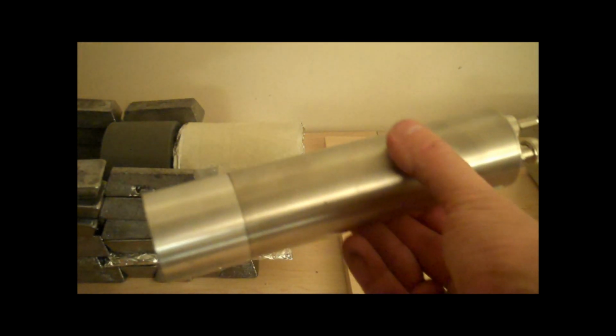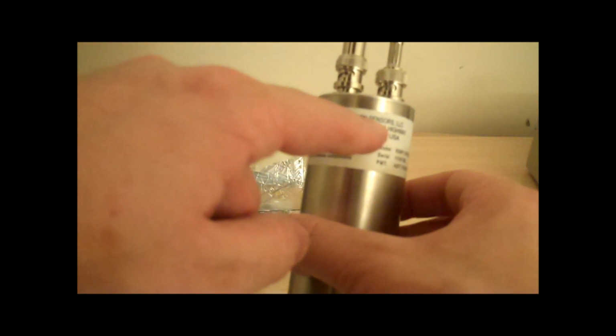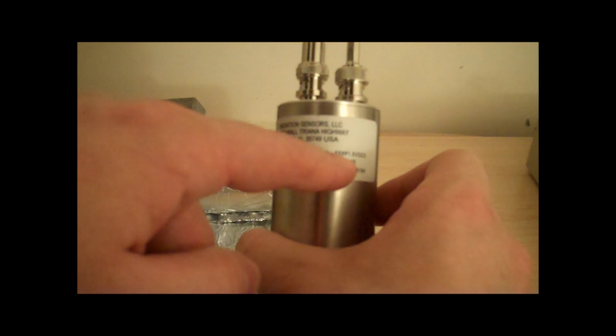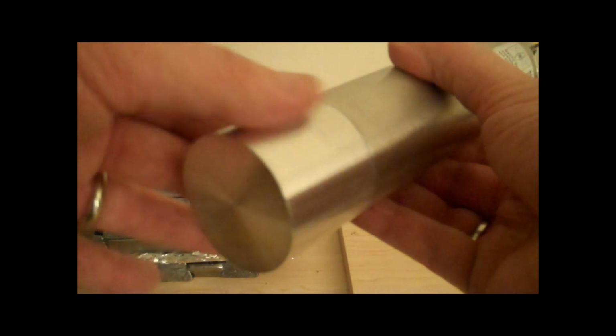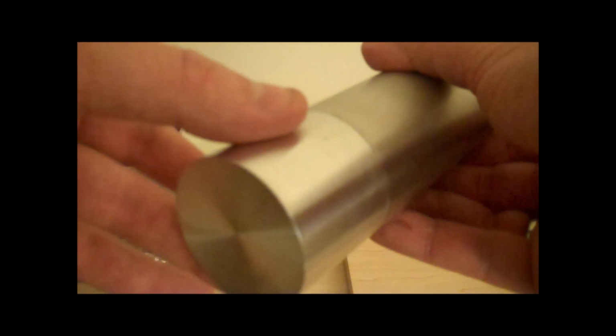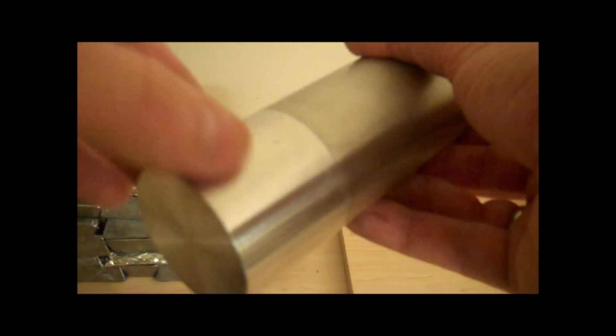This is the scintillation detector. This particular one is a Radiation Sensors LLC model 6S6P1.5VDC2. It has a 38mm sodium iodide crystal that is thallium doped. This is the high voltage input right here, and this is the data coming out right here, the pulses.